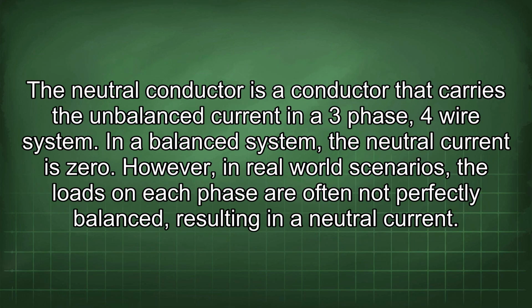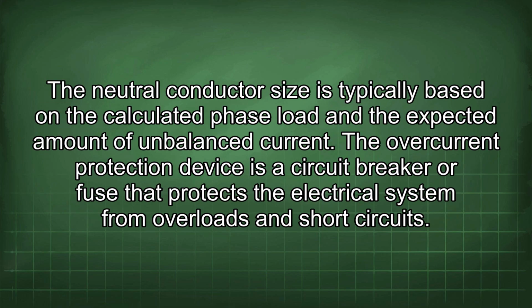The neutral conductor is a conductor that carries the unbalanced current in a 3-phase, 4-wire system. In a balanced system, the neutral current is 0. However, in real-world scenarios, the loads on each phase are often not perfectly balanced, resulting in a neutral current. The neutral conductor size is typically based on the calculated phase load and the expected amount of unbalanced current.